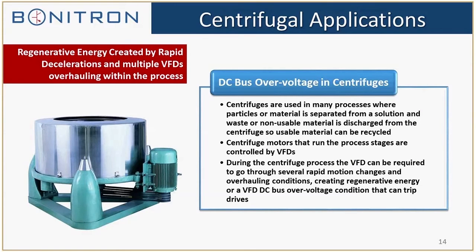One of the larger applications we work with for our regen is centrifuge applications. Just about any larger centrifuge you are dealing with is a high inertia load and you are going to have a very long coast-to-stop. These centrifuges have a deceleration time normally over a minute, so even if they're only stopping the centrifuge two or three times a day, the regen duration is going to be considered a continuous process. Anything over 60 seconds with resistors is going to be considered continuous duty. So if they get a quote for their centrifuge application, they're going to have to get a continuous duty regen.